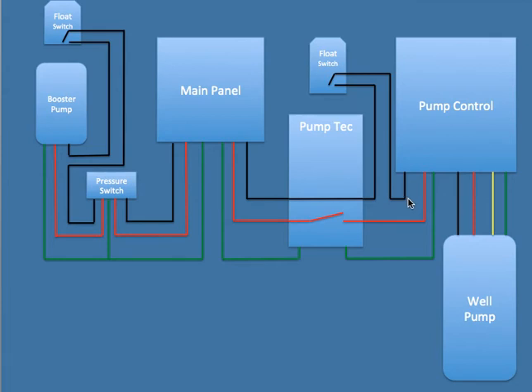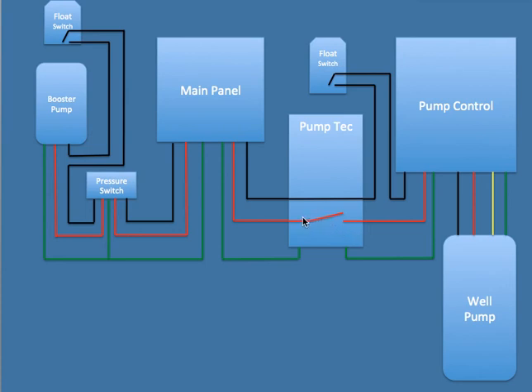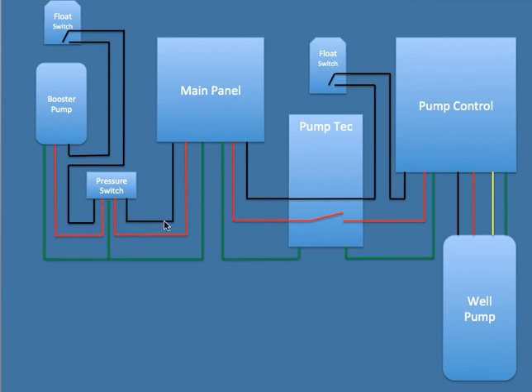If you're looking for a 120 hookup, if your well pump allows you to switch to 120, there might be something in the pump control to switch a jumper or something, then this red wire, just replace it with the white wire. So the white wire will be your 120 neutral, and this will be your 120 hot. Just run the system that way. And then this will disconnect the 120 system. So same thing here, white wire coming out, and then disconnecting the lead wire on the float switch, same principle. So this actually works for both the 240 and the 120.